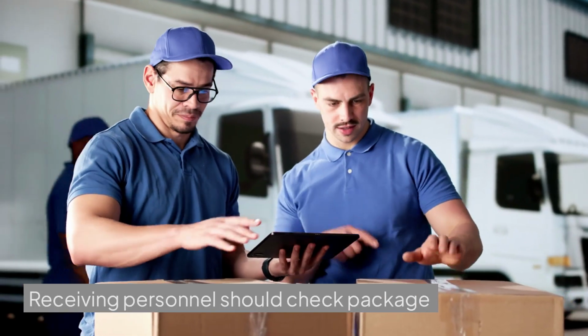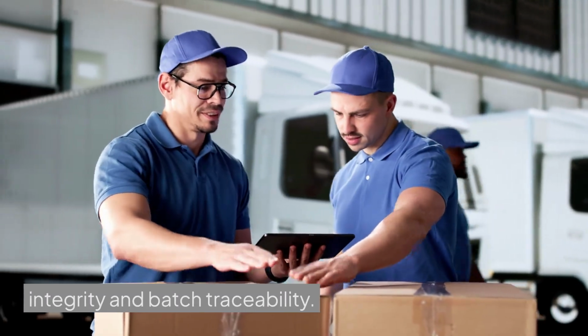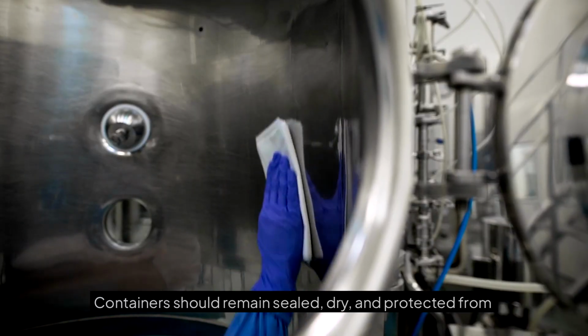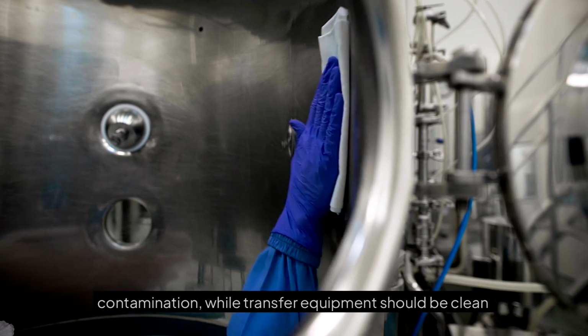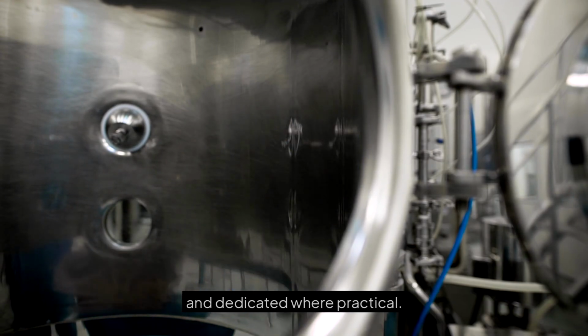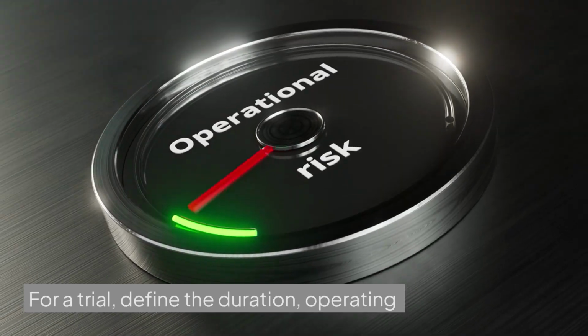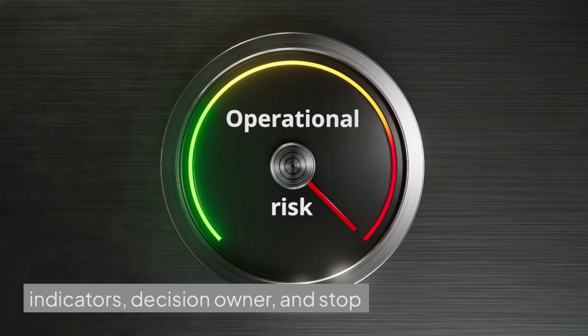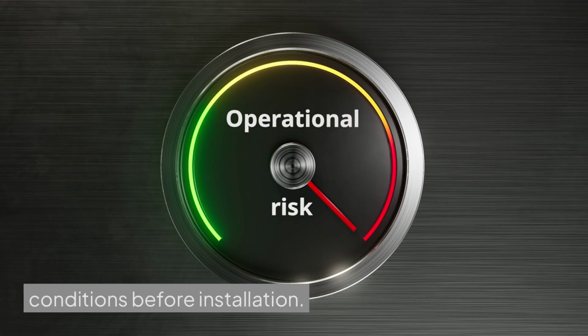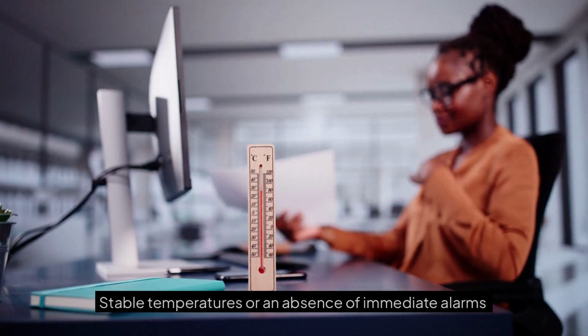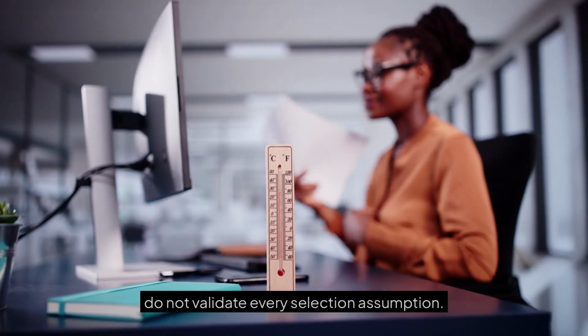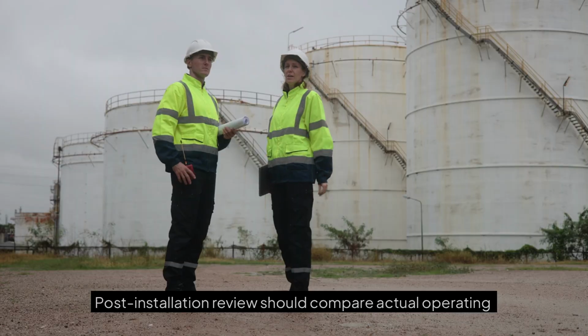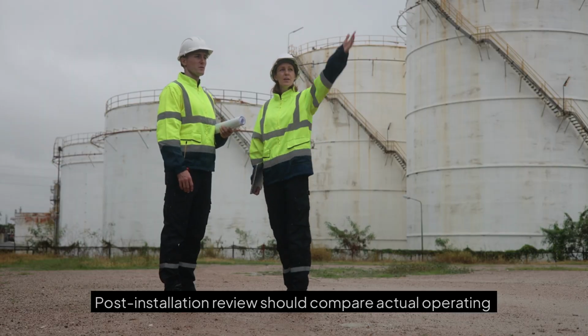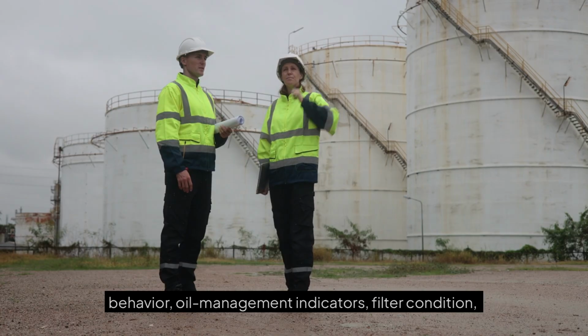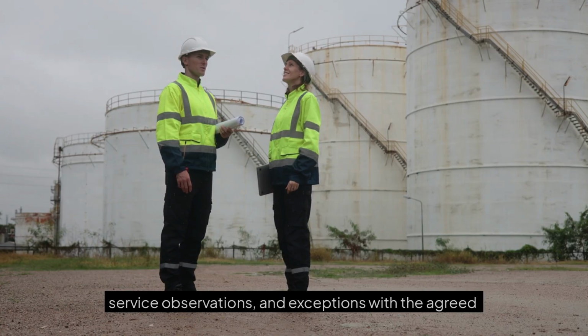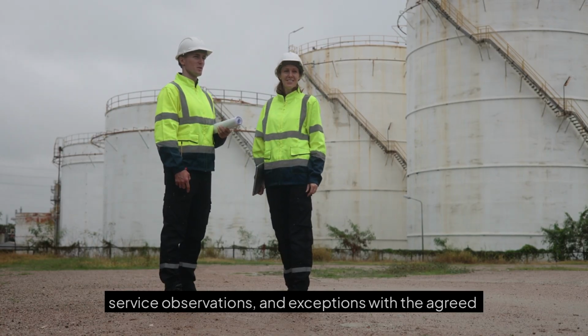Receiving personnel should check package integrity and batch traceability. Containers should remain sealed, dry, and protected from contamination, while transfer equipment should be clean and dedicated where practical. For a trial, define the duration, operating indicators, decision owner, and stop conditions before installation. Stable temperatures or an absence of immediate alarms do not validate every selection assumption. Post-installation review should compare actual operating behavior, oil management indicators, filter condition, service observations, and exceptions with the agreed acceptance criteria.